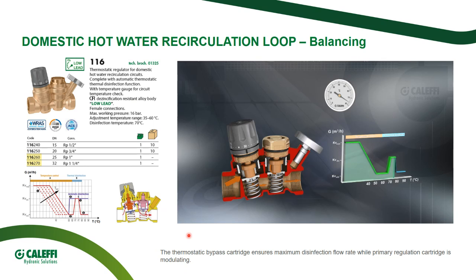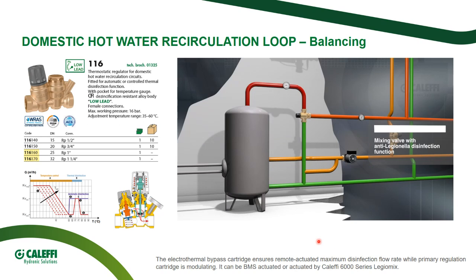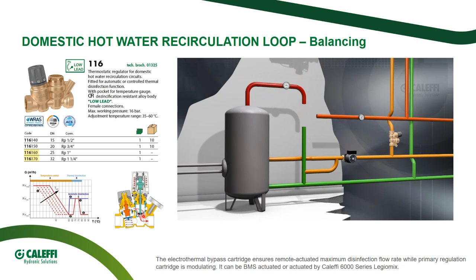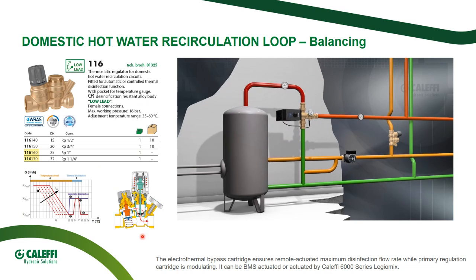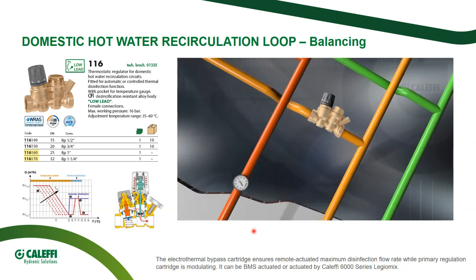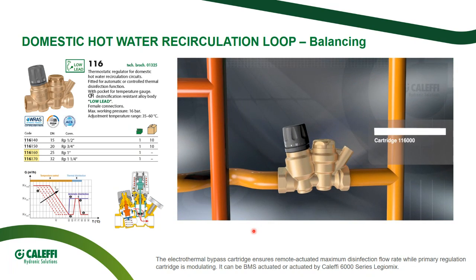So when the digital mixing valve is giving me 70 Celsius degrees, for instance, for the thermal disinfection, the valve will have the maximum bypass flow possible, so I will never miss recirculating disinfection flow rate. The most complete configuration of this family of valve is with electrothermal bypass cartridge, and this is shown in this small video.